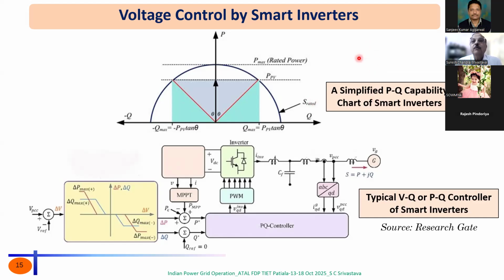So converters being used for solar, which are inverters, should not only be used for interfacing purposes. Their other control features have to be exploited. One feature we can exploit is that at the sacrifice of slight real power, you can generate reactive power. So it is not a reactive power source, but if you know the principle of STATCOM, it works on that principle. It is the play of the vector, like injecting a current at 90 degrees to the voltage, which creates a reactive power effect. So the same effect we can get.